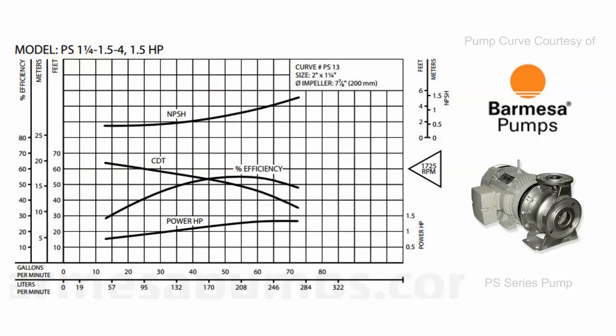This one looks quite different than the curve we looked at before — it shows a lot of information. The first curve I'm going to point out is the performance curve of the pump. This is going to tell us that this pump can produce a maximum head or pressure of approximately 63 feet, and it's going to have a maximum flow rating of approximately 72 gallons per minute. What this particular curve shows that the first one did not is the efficiency curve, which is very interesting.